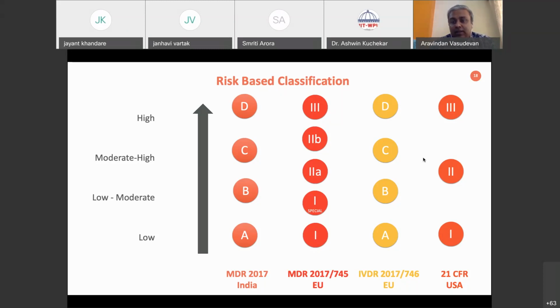The European norms, which are now new, have two different types of classifications. One special is for reusable implements: 2A, 2B, and 3. And for the IVDR they have a pretty simple A, B, C, D. And the US FDA still uses a very simple classification called 1, 2, and 3. So either you are in class 1, class 2, or class 3. This is where your device falls.